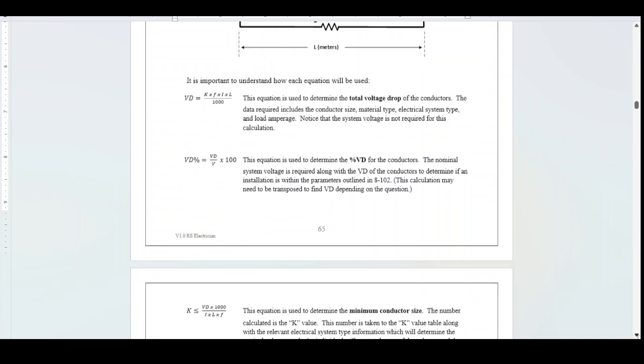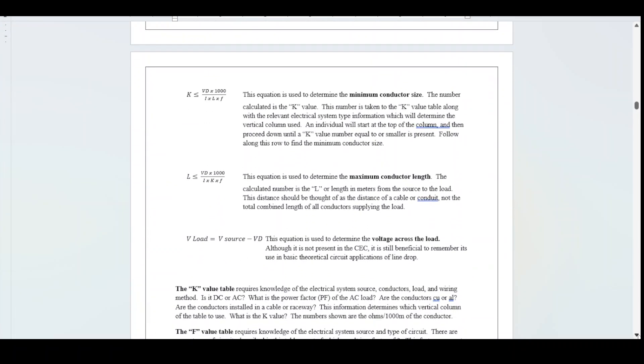Let's take a look at some more equations. This equation is used to determine the minimum conductor size. The number calculated is the K-value. This number is taken to the K-value table, along with the relevant electrical system type information, which will determine the vertical column used. An individual will start at the top of the column and proceed down until a K-value number equal to or smaller is present, then follow along that row to find the minimum conductor size.